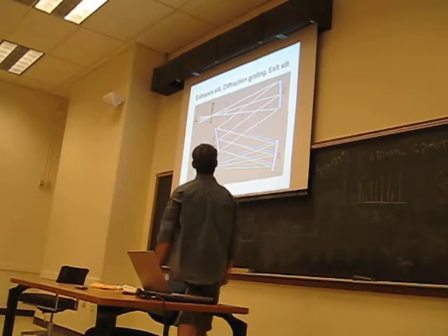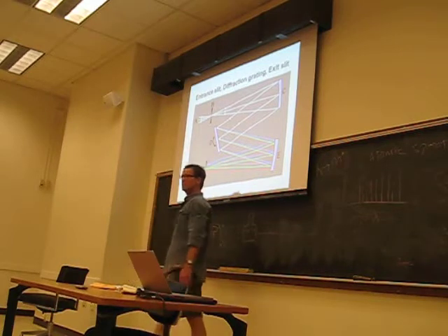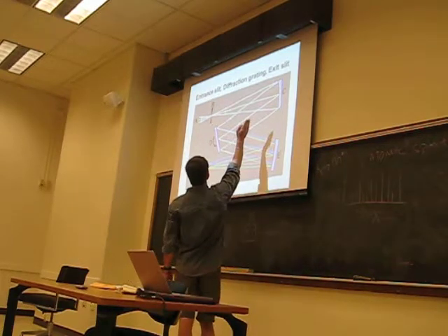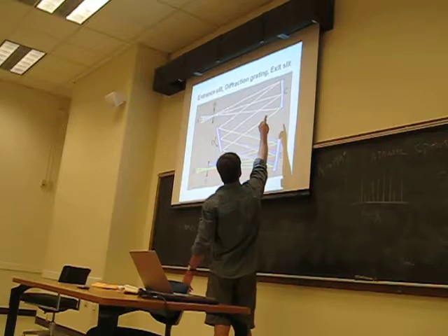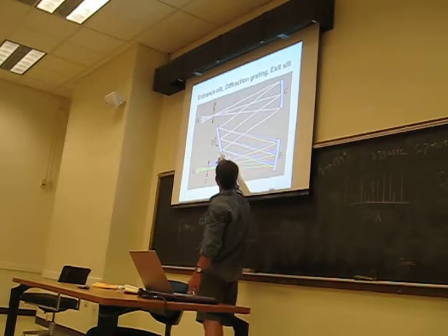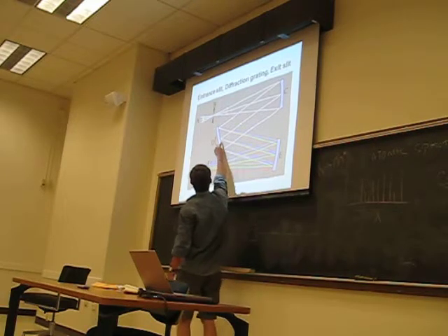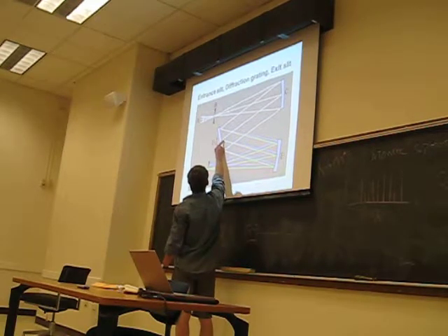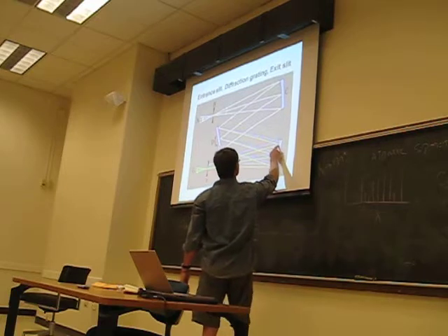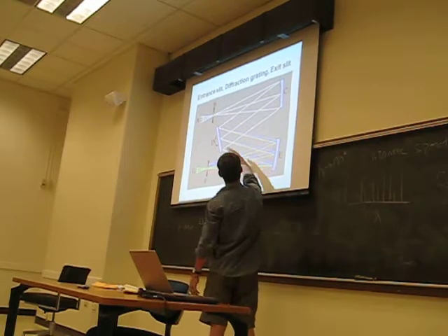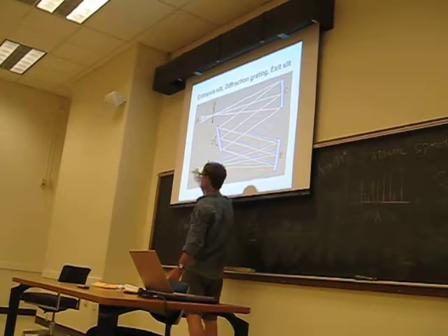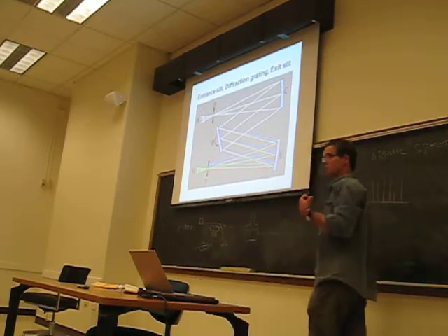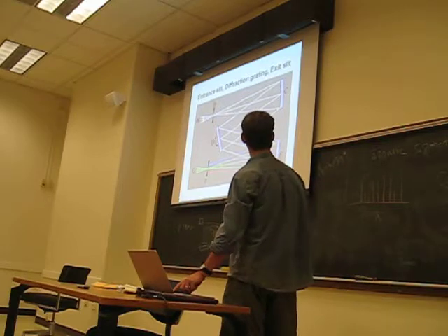So here's the light source going through an entrance slit, okay? And it's all white light, and it contains three spectral lines for copper, let's say, and it is reflected through this concave mirror to the diffraction grating that can rotate. The grating is now separating that polychromatic light into its multiple components, reflecting the different wavelengths at different angles, and now they come out at separated wavelengths. It's moved the diffraction angle on the grating so that you're selecting for the green light and not the red and blue light. So it's pretty straightforward that way. It's a pretty ingenious way to achieve that control.